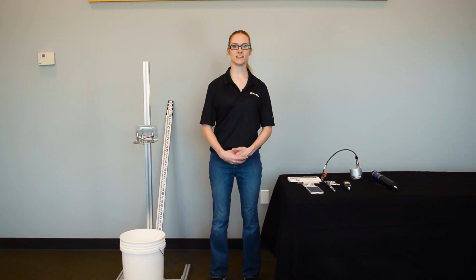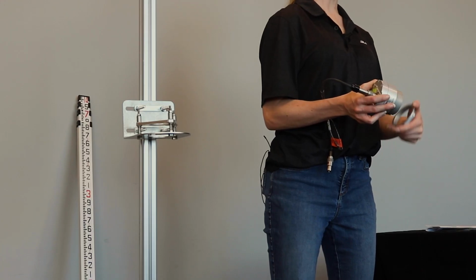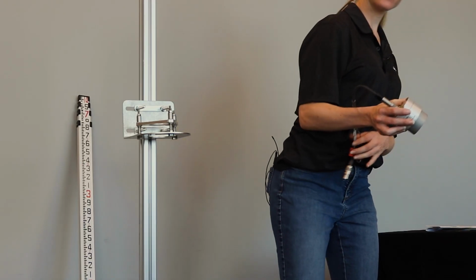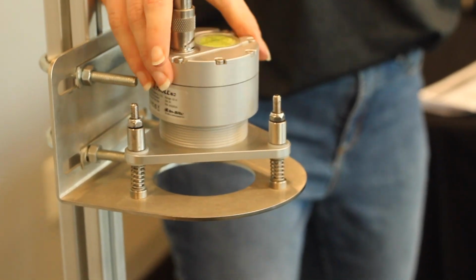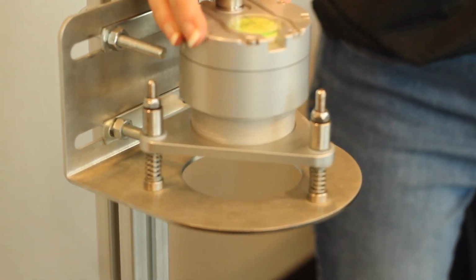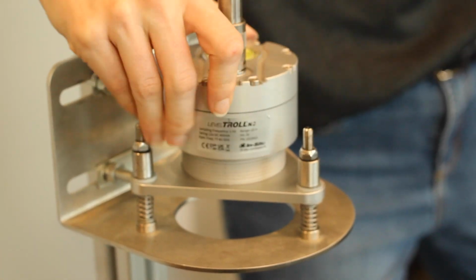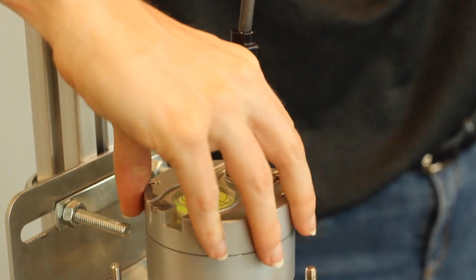Once you have your bracket installed, remove the nut from the bottom of the instrument and thread the instrument into the bracket. It may be easier to disconnect the cable to do this, depending on what your deployment setup looks like. After you've installed your instrument, reconnect the cable.